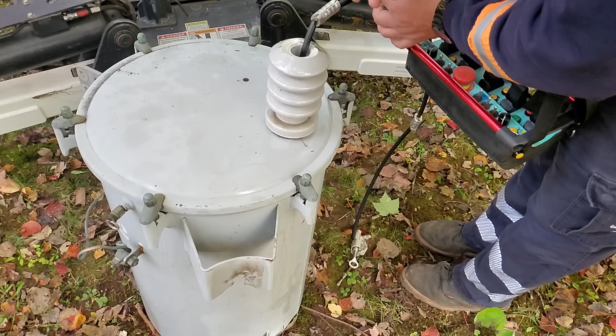We did some investigating and discovered this was a storm repair. It wasn't one of our crews that made the repair, but a tree had fallen on the line. Let's see if one of these photos shows the fence. Anyway, you could see where the fence was hit by the tree, and it busted the top bushing on the transformer. It was a difficult area to access, so it wouldn't have been that big of a job to change the transformer, just more of a slight inconvenience to get to the backlot.